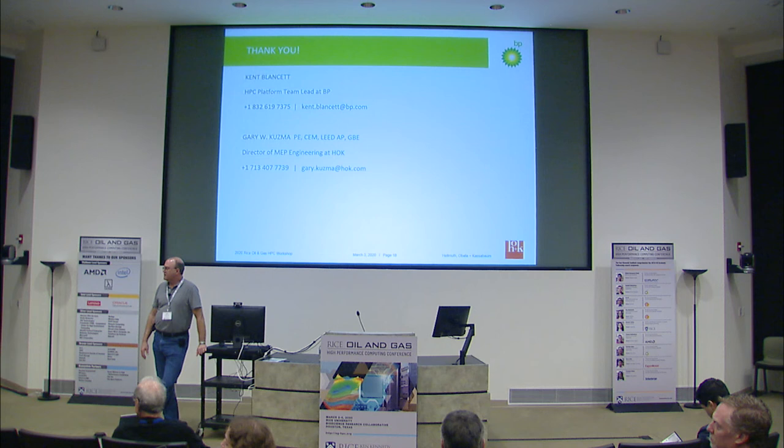Audience comment and question: Please accept my sympathy if you ever have to put pink dye in the system to find a leak. Kent's response: I would avoid it — it's green and it shows up with UV light. On the 400-volt racks: do you have any additional safety precautions for people around that voltage? Kent's response: They're all pin and sleeve connectors. We've not had any concerns raised. We checked on that. Most of our other racks are actually 480 volt, but 415 volt is doable by all vendors.